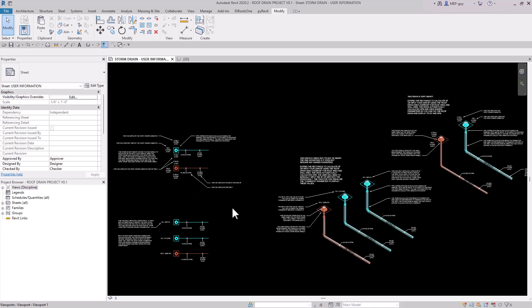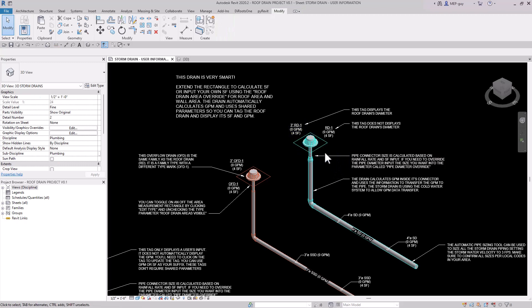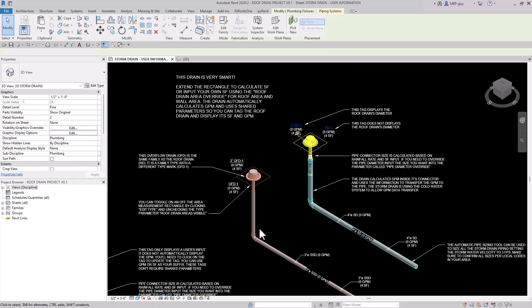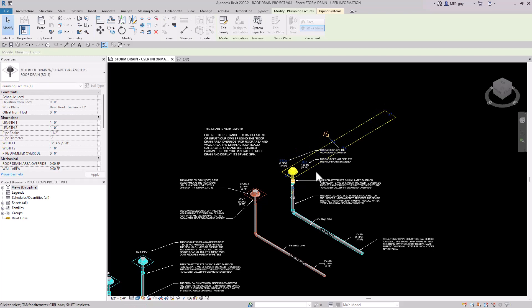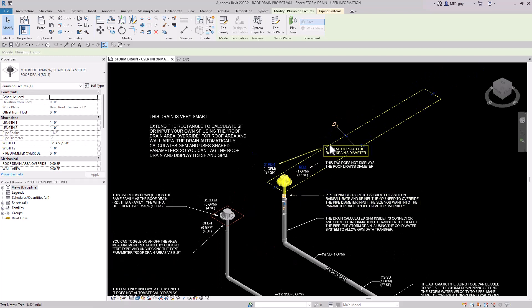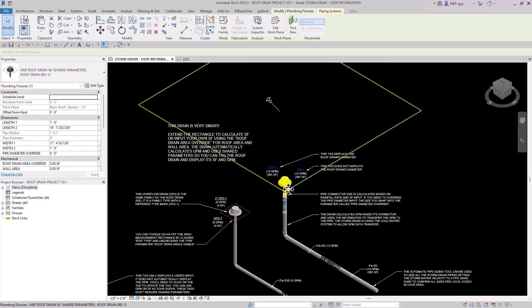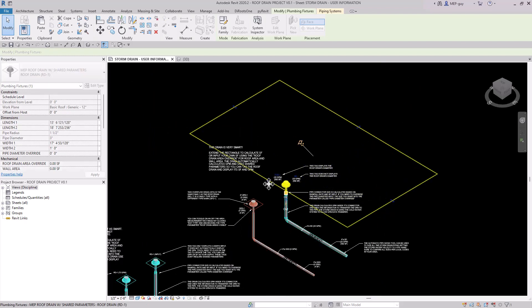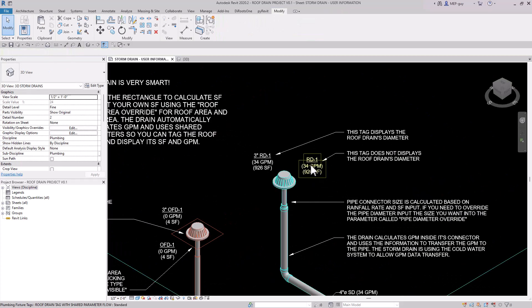Let me show you guys how these roof drains work. I'm going to zoom in and double click into this view. You can see the roof drain has a little box or rectangle around it, which helps calculate the square footage. This square footage calculation gets converted to GPMs. I'm going to click on the roof drain family — you can see these little grips. As I move the grip out, the GPM and square footage start to increase. I'm up to 361 square feet and 13 GPM.